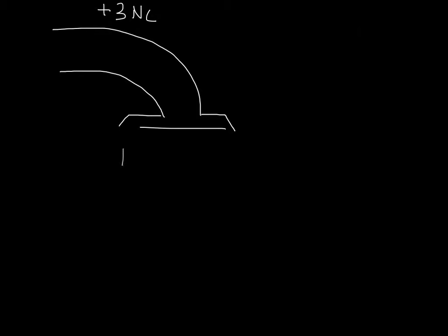The next best option would be a soft radius of flex duct, kind of like this. This will add about 3 NC to our diffuser data, so now it'll be an NC28 installation.